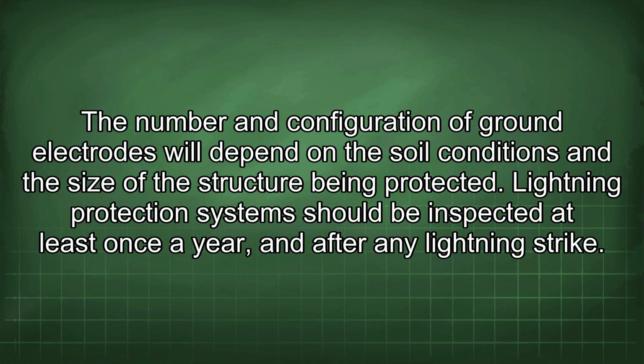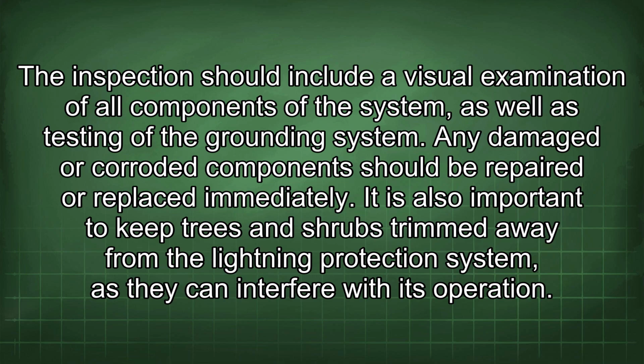Lightning protection systems should be inspected at least once a year, and after any lightning strike. The inspection should include a visual examination of all components of the system, as well as testing of the grounding system. Any damaged or corroded components should be repaired or replaced immediately. It is also important to keep trees and shrubs trimmed away from the lightning protection system, as they can interfere with its operation.